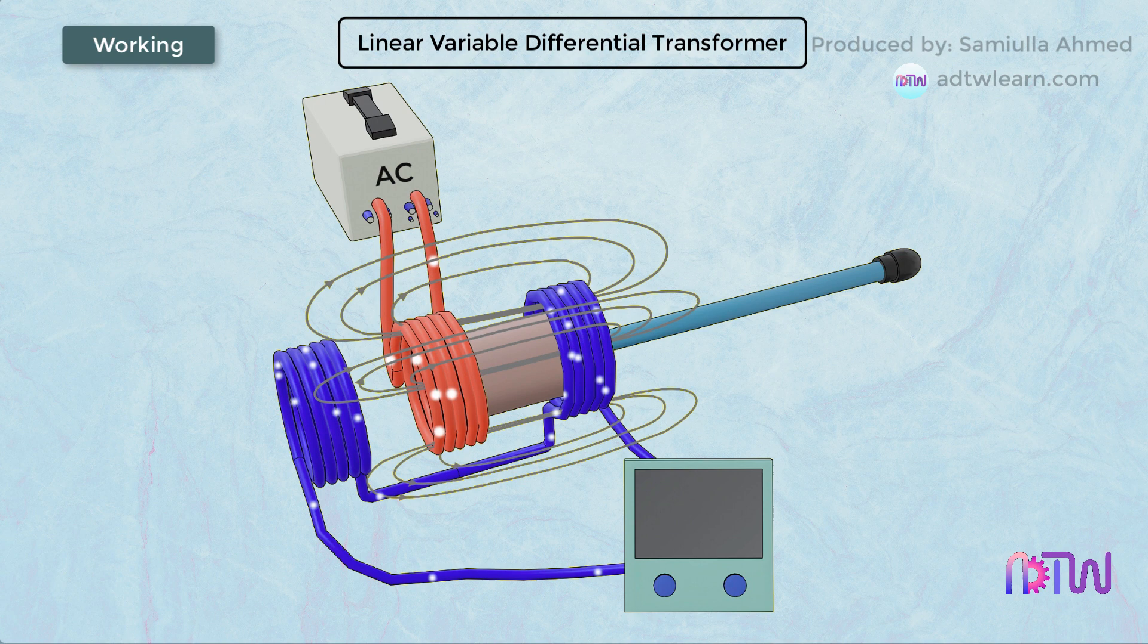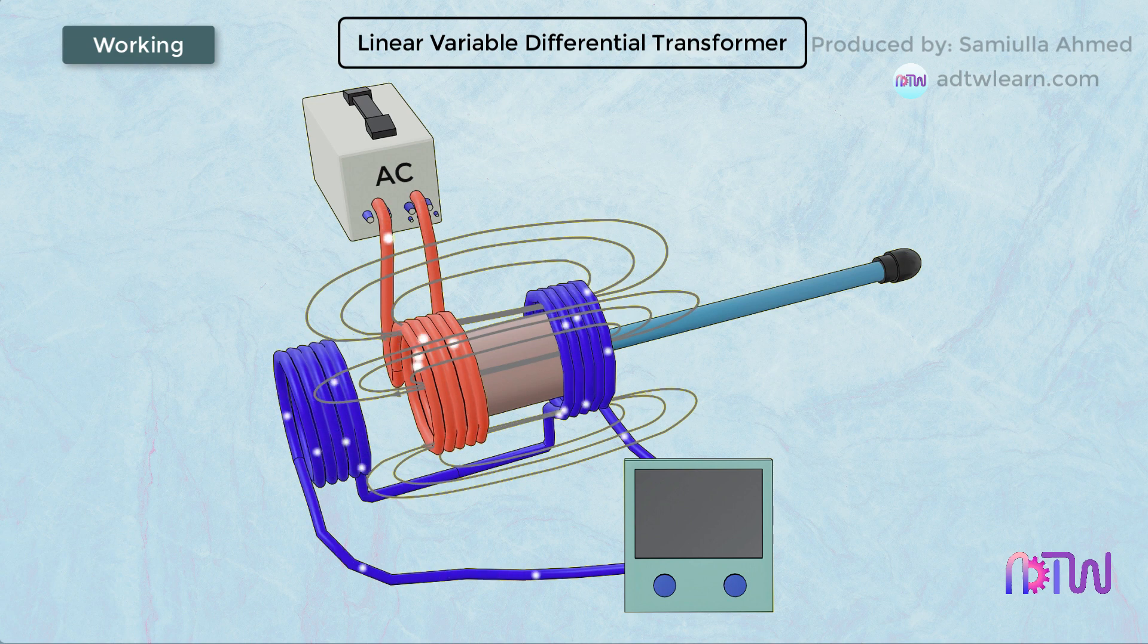Thus we can conclude that the amount of EMF induced in the pair of secondary windings is proportional to the displacement of the movable iron core. This output voltage can be measured to determine the relative position or displacement of the iron core. The output voltage is a linear function of the core displacement.